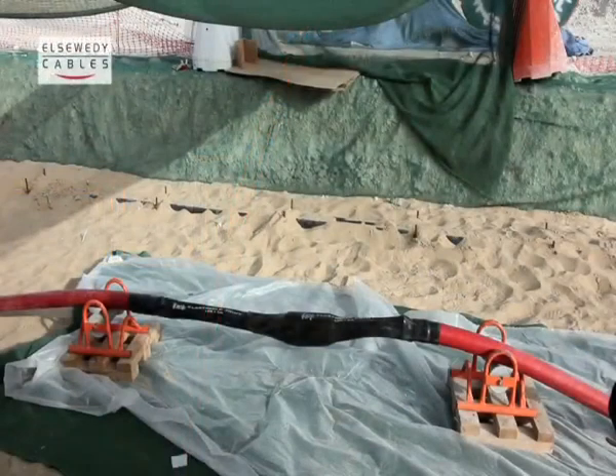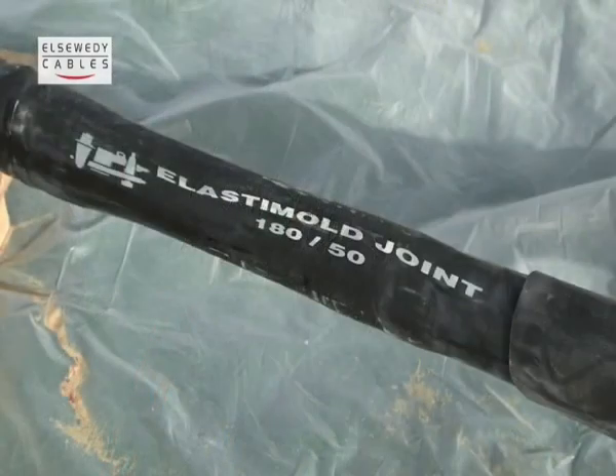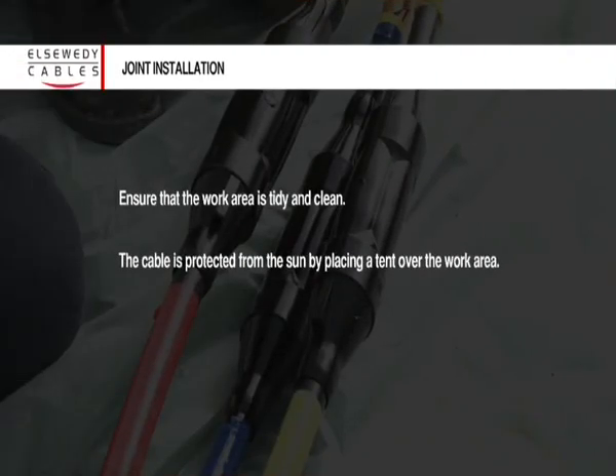The process of joint installation is a delicate process that needs to be executed with care and complete concentration. Detailed instructions are provided along with the Elastimold pre-molded joint. Before beginning the process of joint installation, ensure that the work area is tidy and clean. The cable is clean and protected from the sun. This is done by placing a tent over the work area.